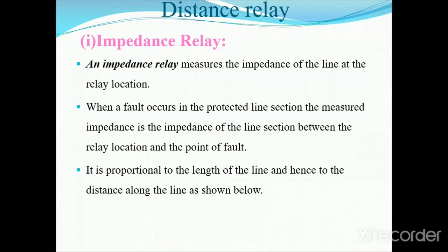Okay, the impedance of the relay settings, it gives the tripping command to the circuit breaker for closing their contacts. Okay, if the ratio of voltage and current is less than the relay setting, then the relay starts operating. In that case only the circuit breaker will be operated.